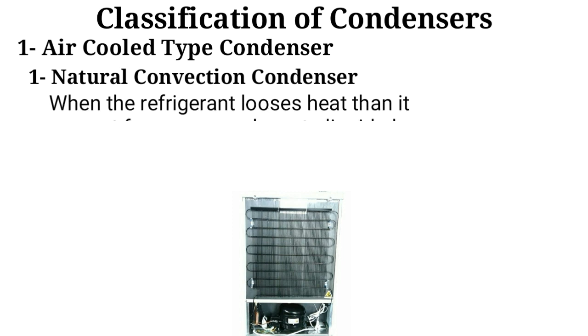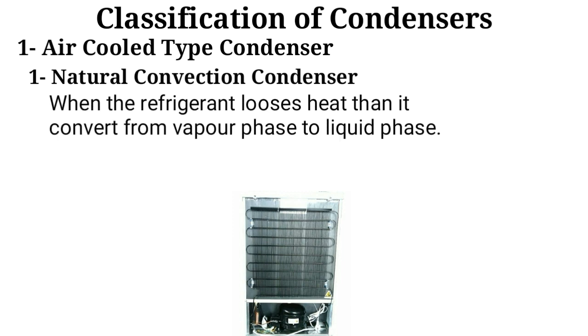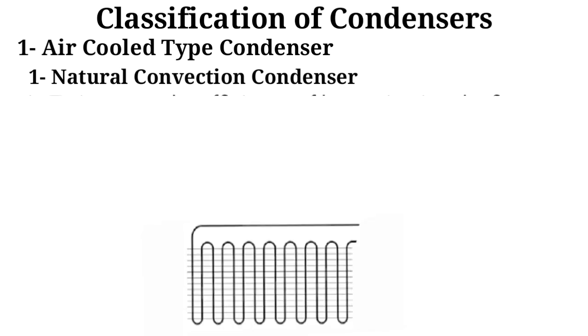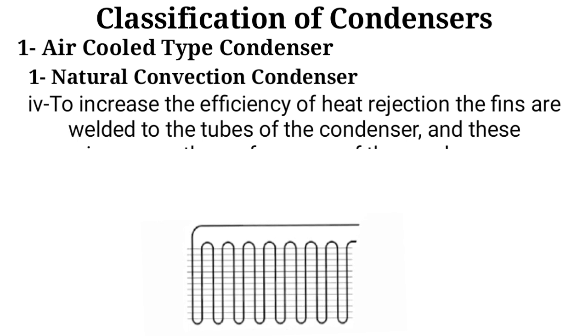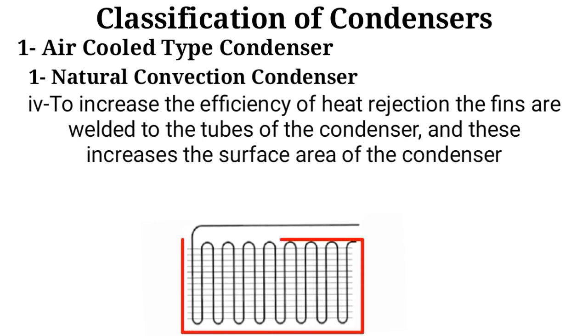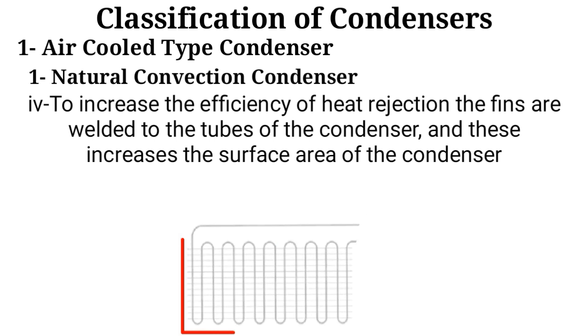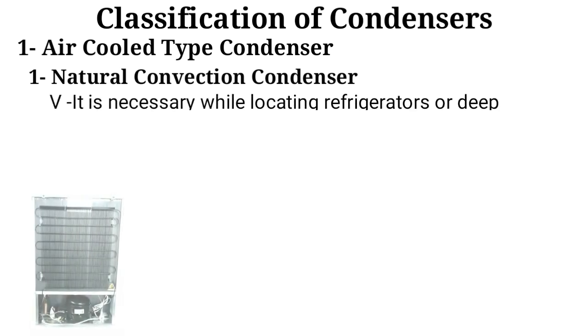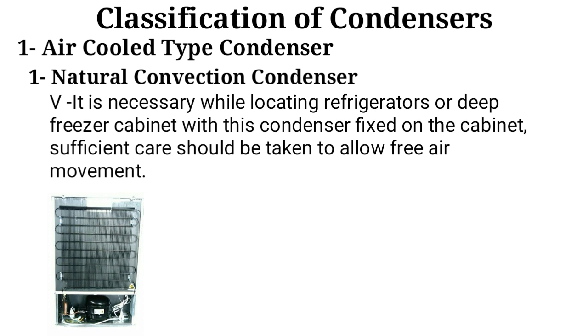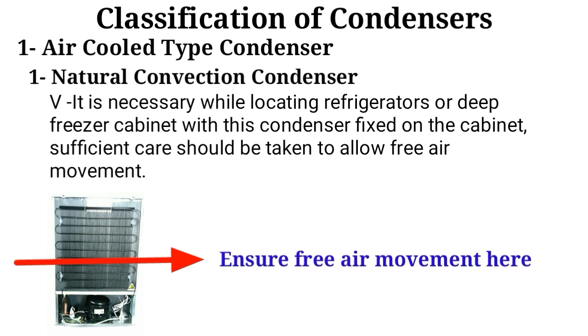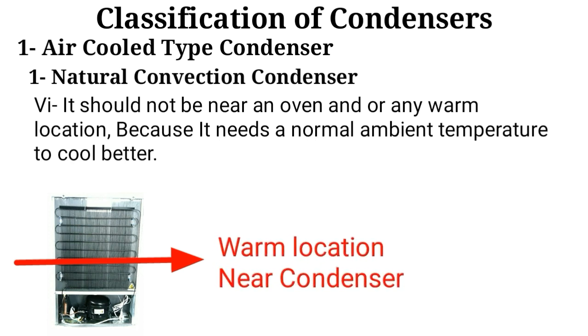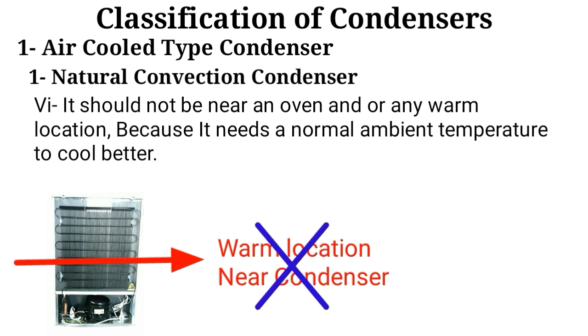When the refrigerant loses its heat, it changes from the hot vapor phase to liquid phase. To increase the efficiency of heat rejection, fins are welded to the tubes of the condenser, increasing the surface area. When locating refrigerators or freezer cabinets with this type of condenser, sufficient care should be taken to allow free air movement. It should not be near any warm location, because it needs normal ambient temperature to cool better.